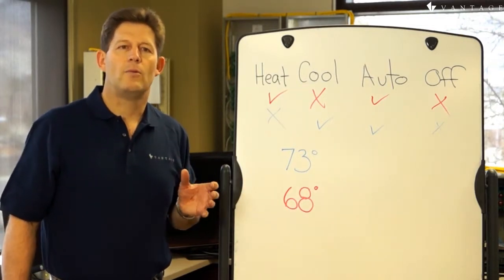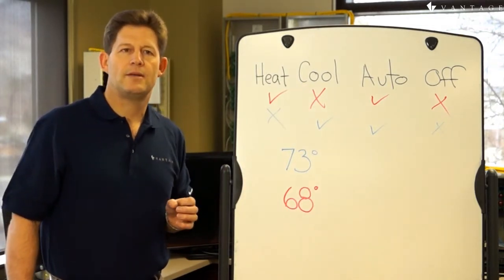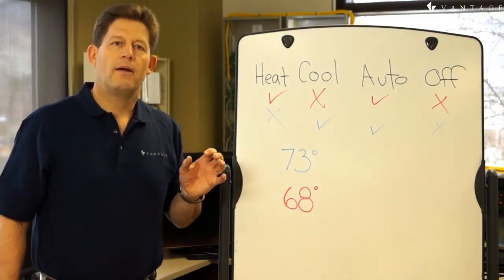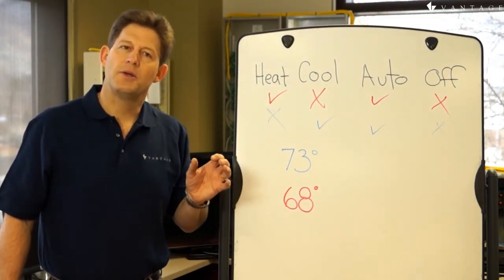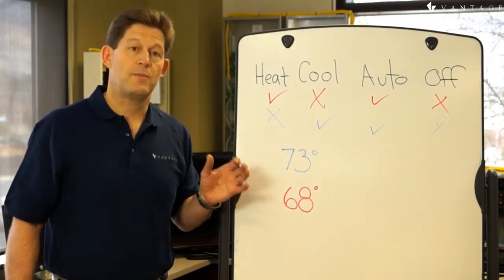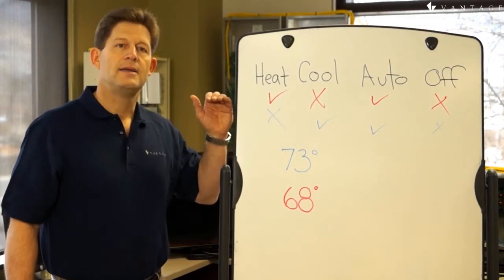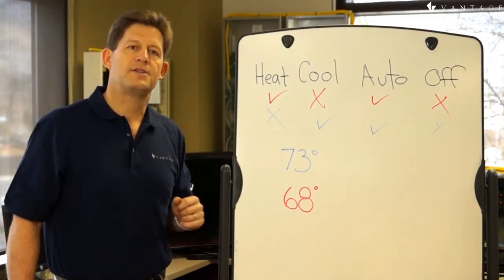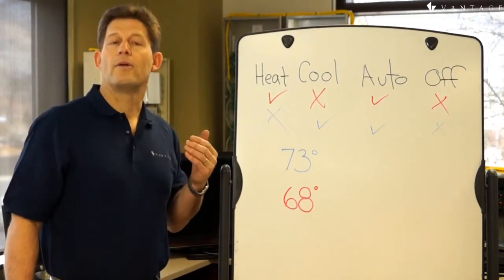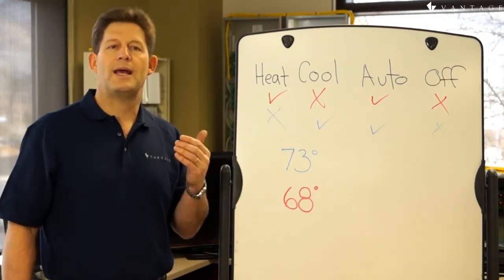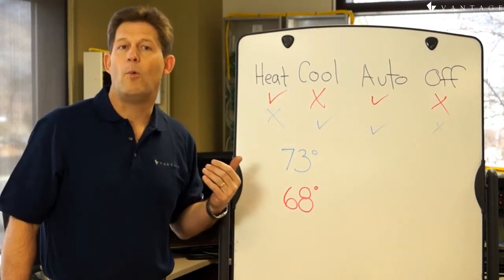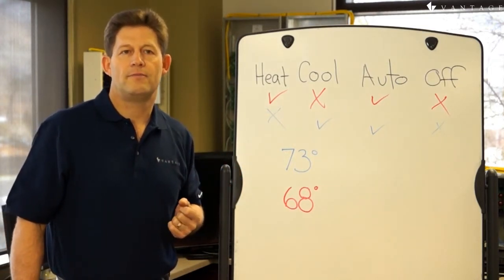So when or why would we only use heat or only cool modes? If we are in the winter and never expect cooling to be needed, the heat mode will produce the same results as the auto mode where the cool set point is set sufficiently high to assure the air conditioner never runs. The typical reason to apply a heat-only or cool-only mode is when we're in a transitional season.